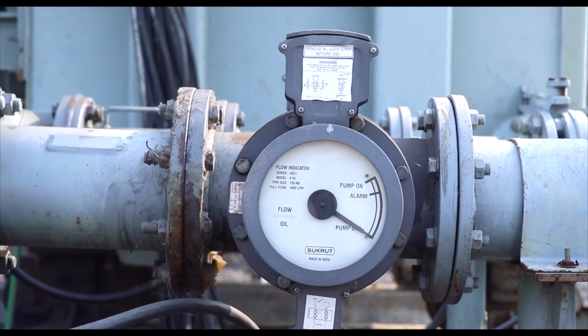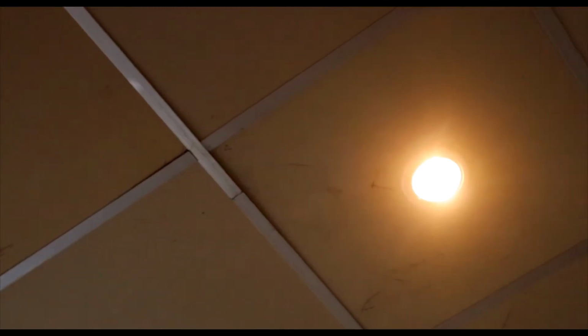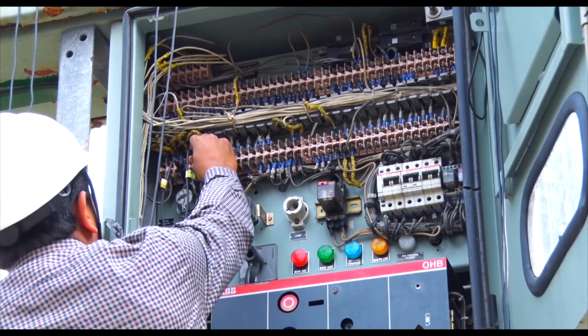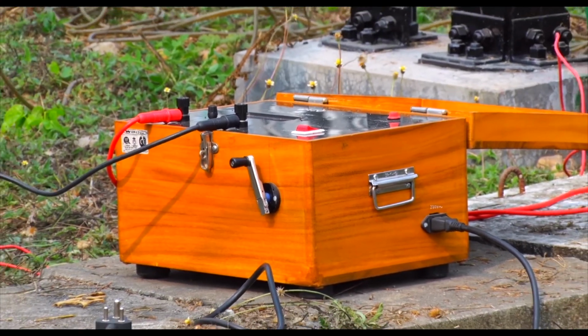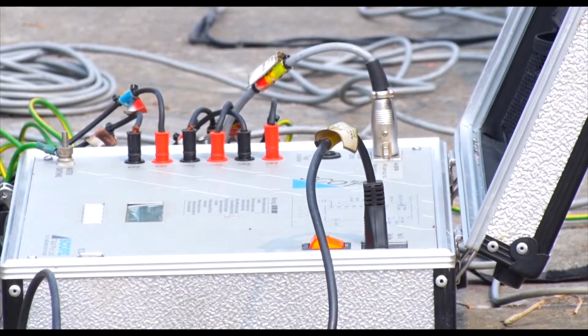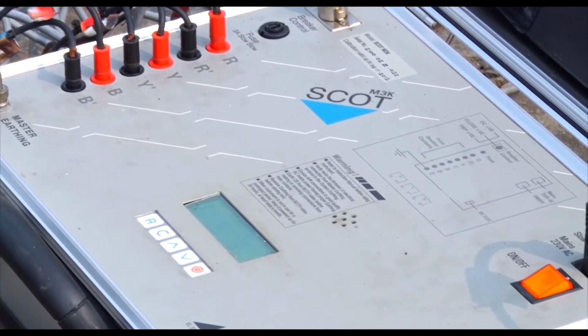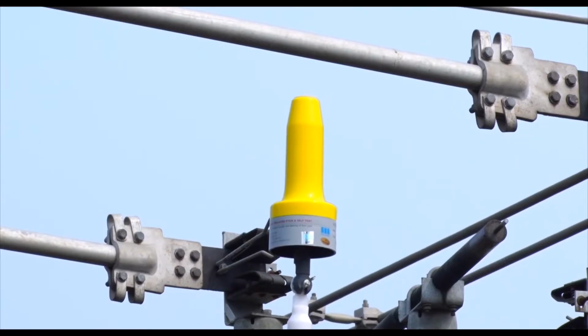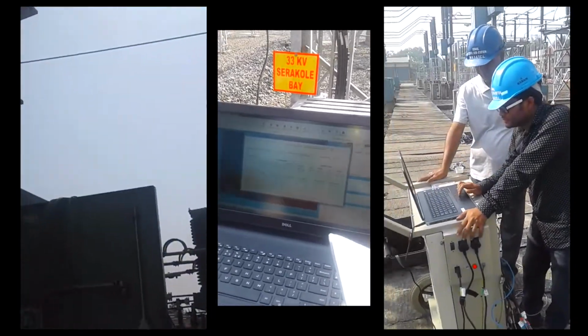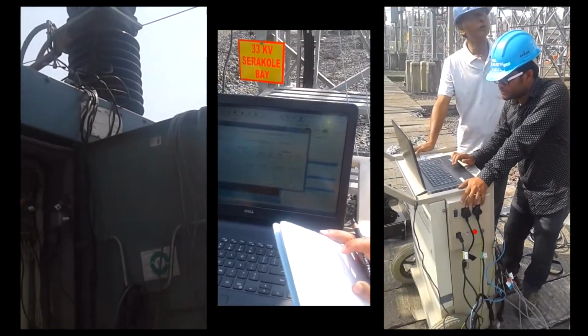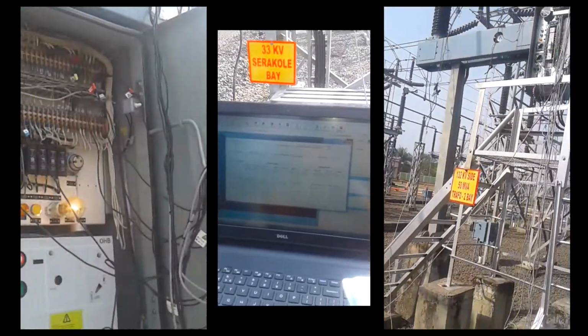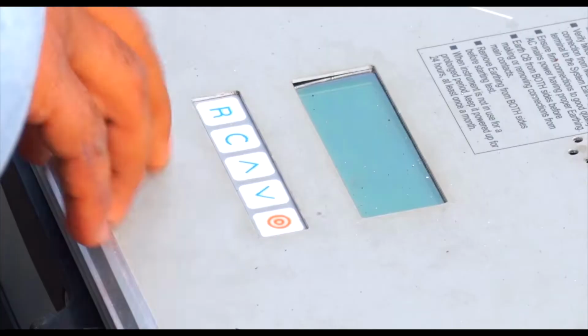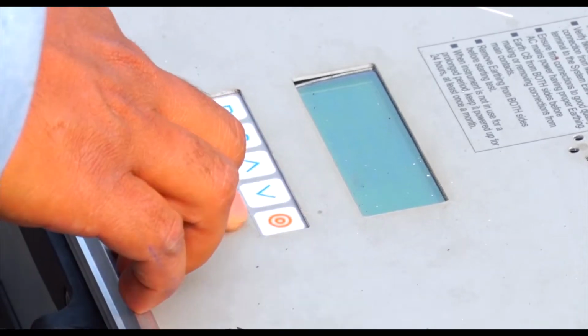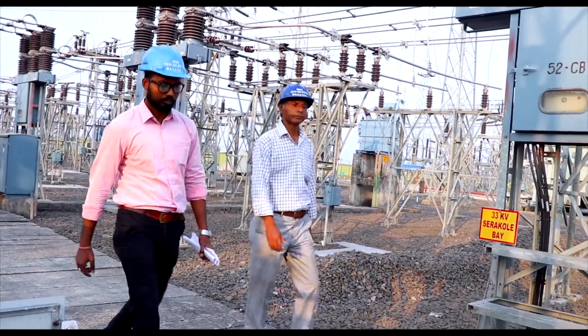The working environment in the substation deals with so many technical aspects of different equipment to maintain the proper healthiness of the power utility and reliability. So many advanced technical tests like DCRM, tan delta, Megger, earth resistance measurement, CB timer, infrared ultrasound healthiness scanning of LA and various insulator strings, hotspot checking, BDV of oil and so many periodical routine maintenance including line patrolling as per requirement.